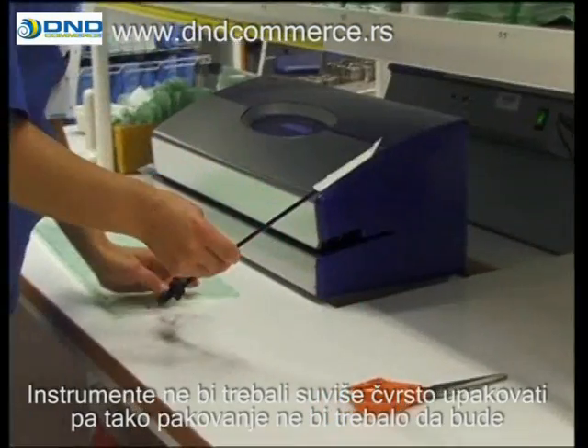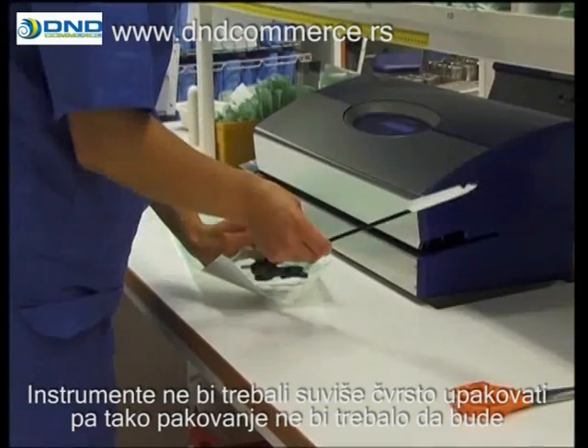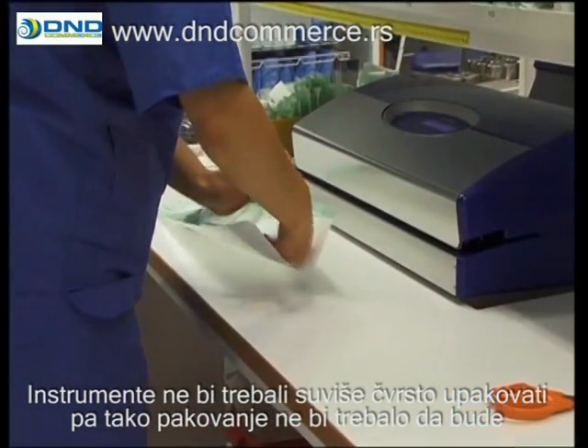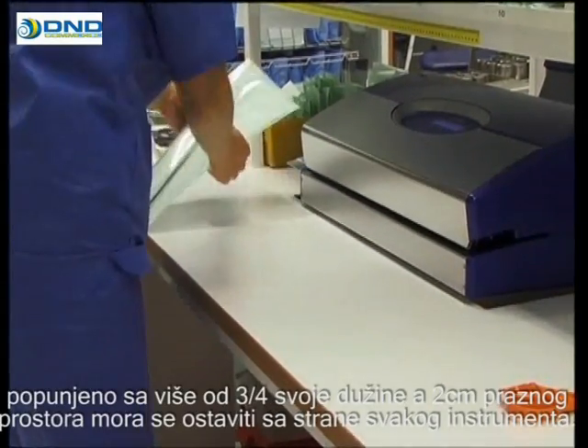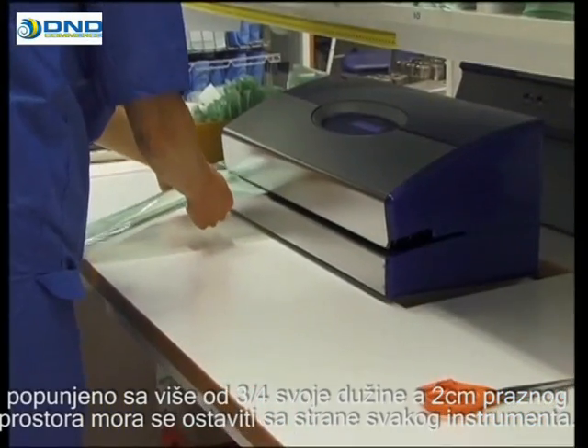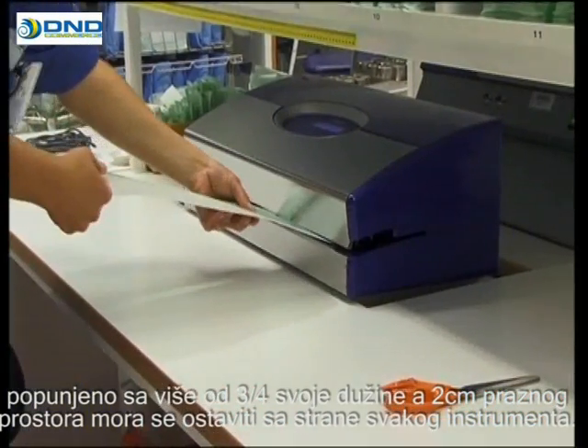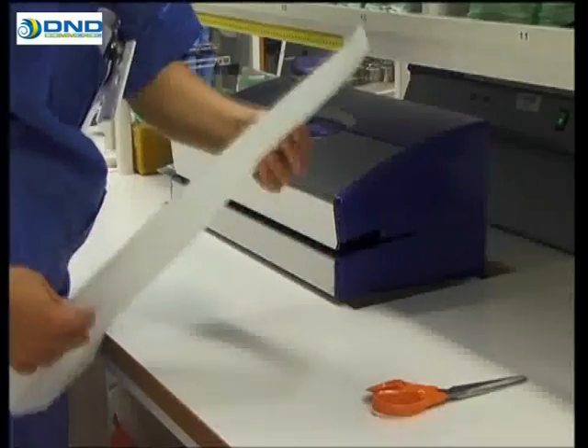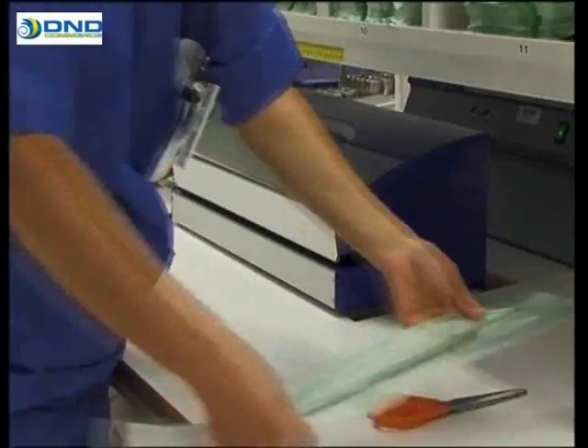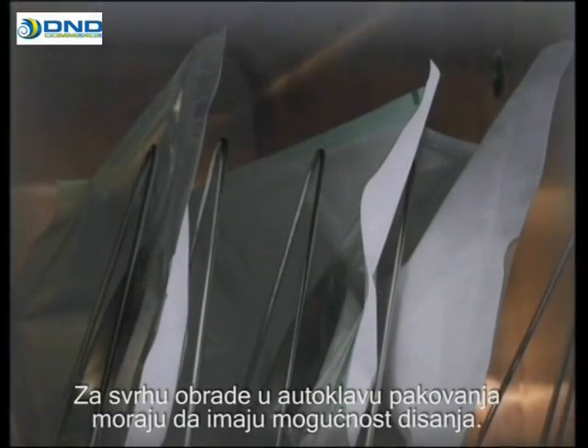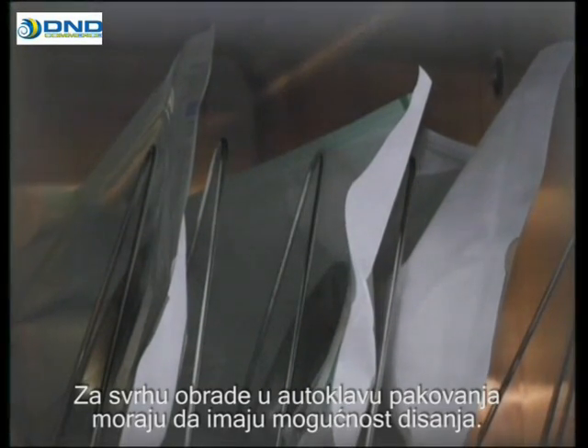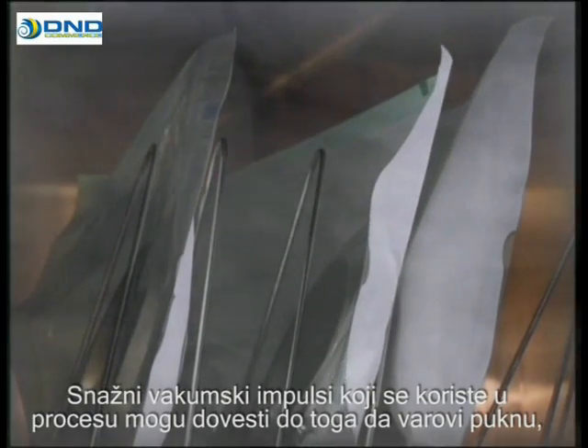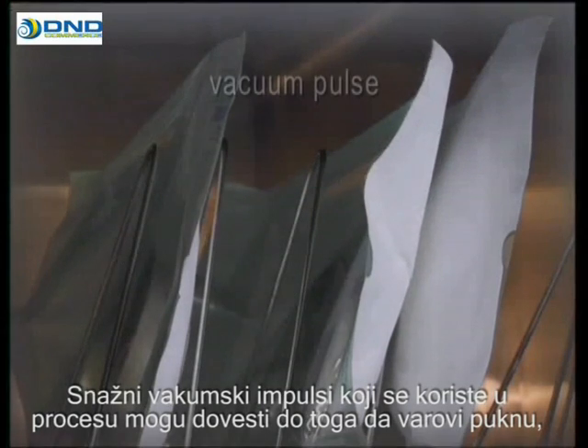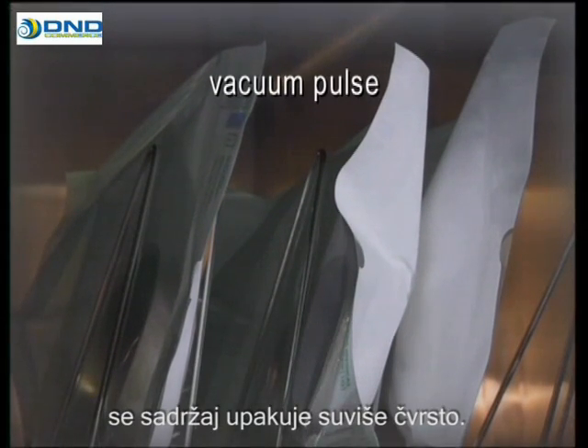The instruments should not be packed too tightly. It's recommended that the packages should be filled to no more than 3/4 of their length, and 2 centimeters of empty space should be allowed around each instrument. For the purpose of autoclaving, the packages must be able to breathe. The powerful vacuum pulses used in the process can cause the seals to break open if the contents are packed too tightly.